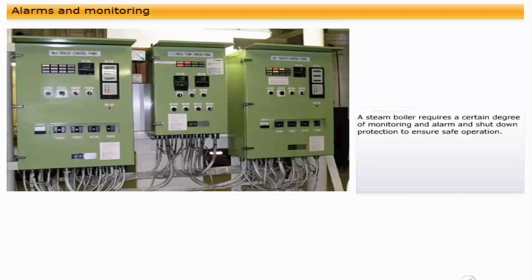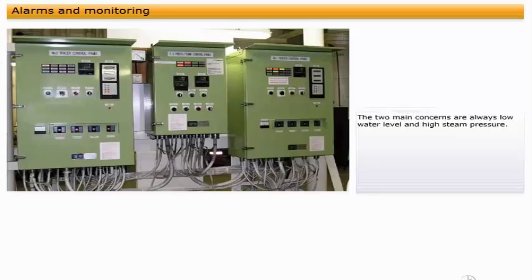A steam boiler requires a certain degree of monitoring and alarm and shutdown protection to ensure safe operation. The two main concerns are always low water level and high steam pressure. A very low water level can result in overheating, resulting in boiler failure. This is often termed low-low level.